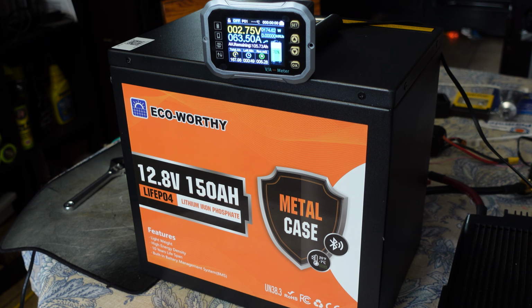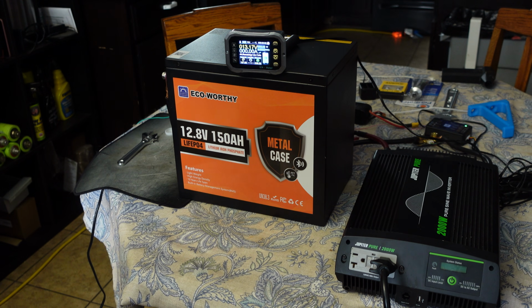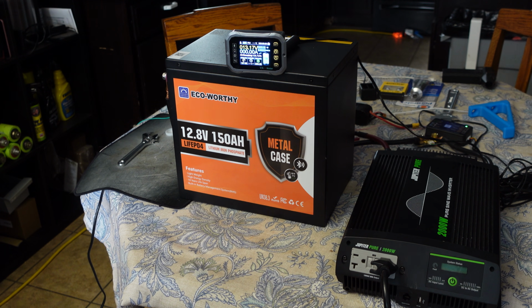Oh, there it went, the battery just tripped. So that does seem to be about the max you can get. The battery was able to pull 120 amps just fine, but as soon as I went over 120, we were at 127, the battery did shut down after about 10 seconds.